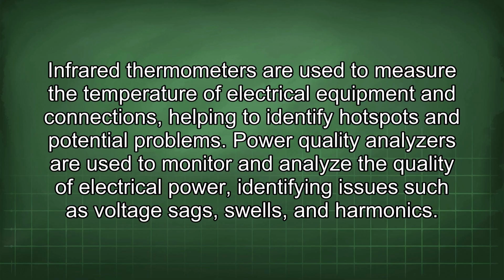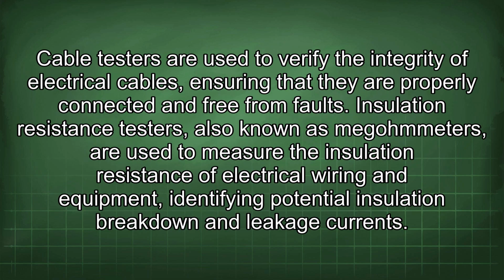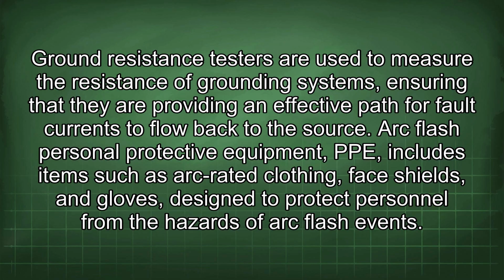and potential problems. Power quality analyzers are used to monitor and analyze the quality of electrical power, identifying issues such as voltage sags, swells, and harmonics. Cable testers are used to verify the integrity of electrical cables, ensuring that they are properly connected and free from faults. Insulation resistance testers, also known as megohmmeters, are used to measure the insulation resistance of electrical wiring and equipment, identifying potential insulation breakdown and leakage currents. Ground resistance testers are used to measure the resistance of grounding systems, ensuring that they are providing an effective path for fault currents to flow back to the source.